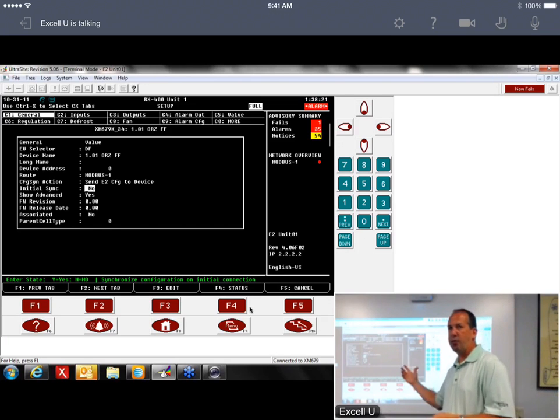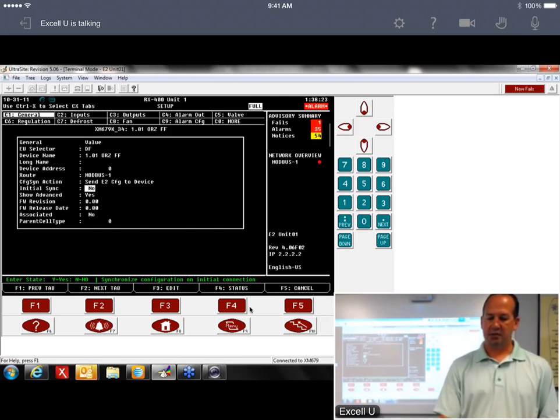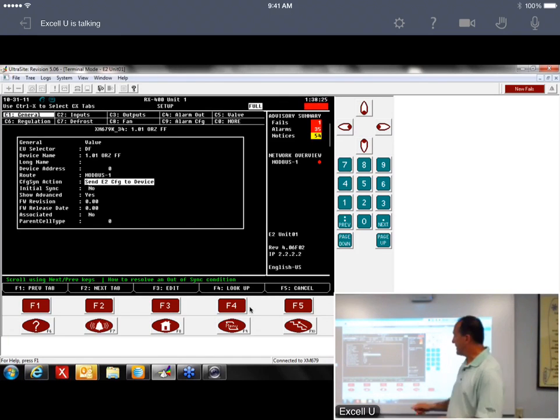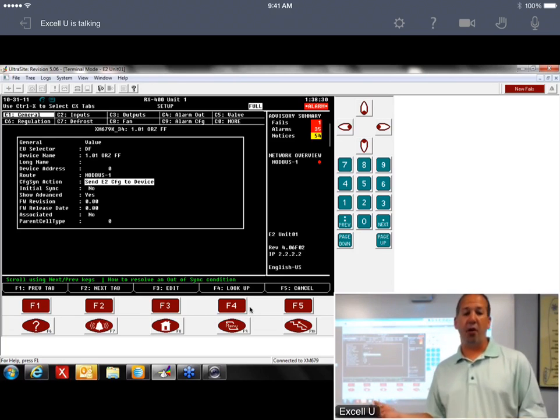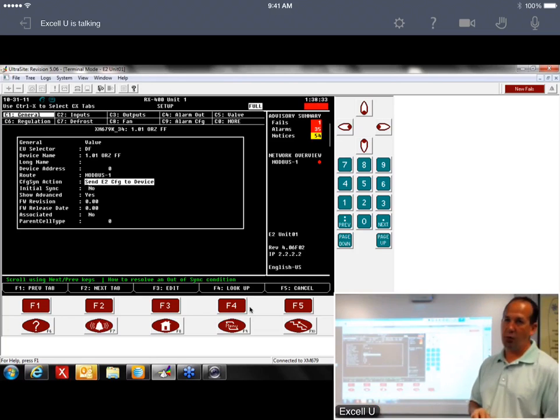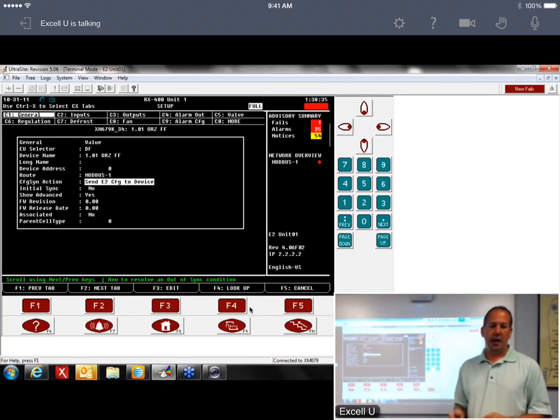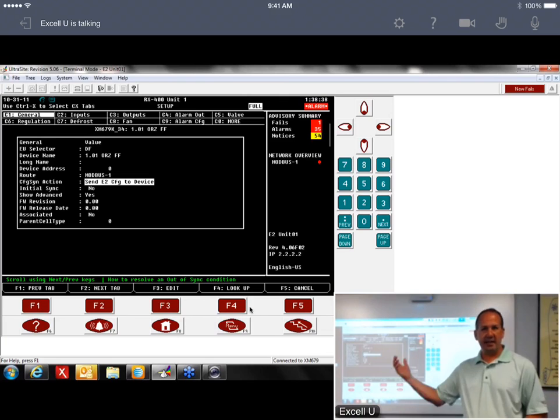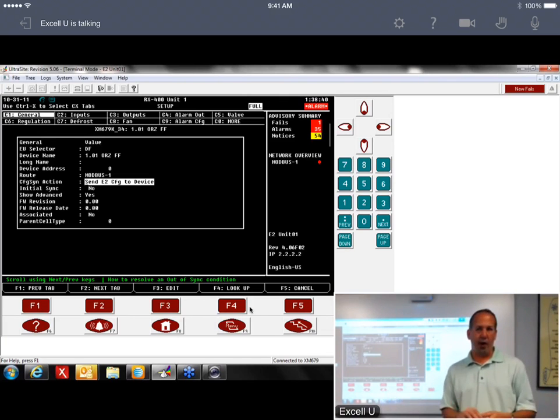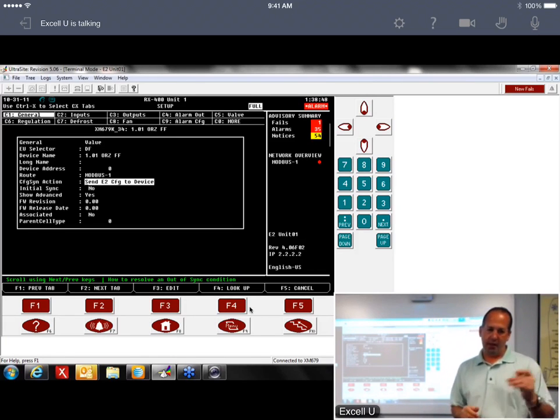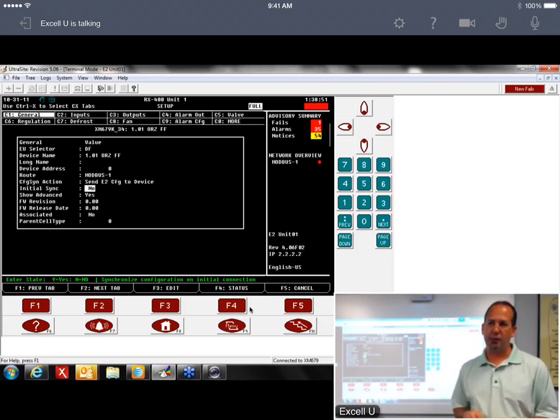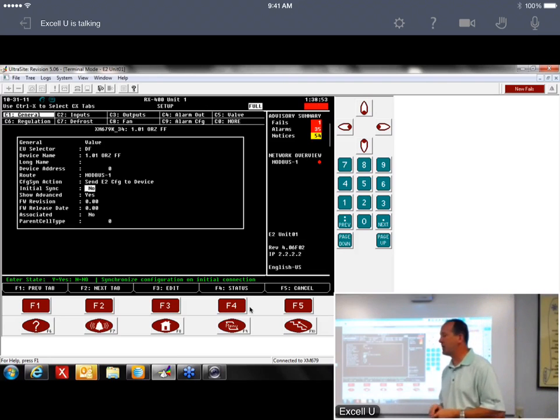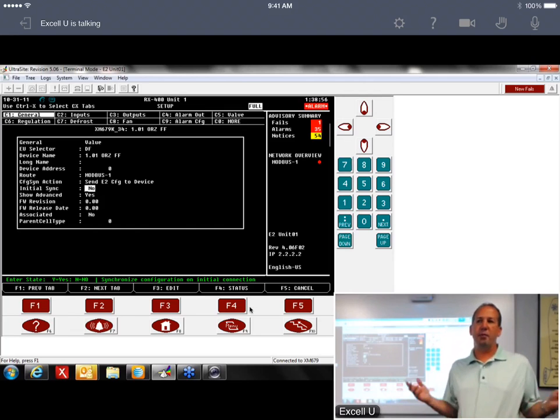We want to take the E2 parameters and push them into that device. So this other one, right above it, config sync action, defaults to send the E2 configuration to the device. What that does is twice a day, it makes sure the device and the E2 are on the same page, have the same parameters. Twice a day it sends the E2's config down to the device. But the initial sync is for when you first power it up. So as long as you have that set, when you first power it up, nothing's going to happen.